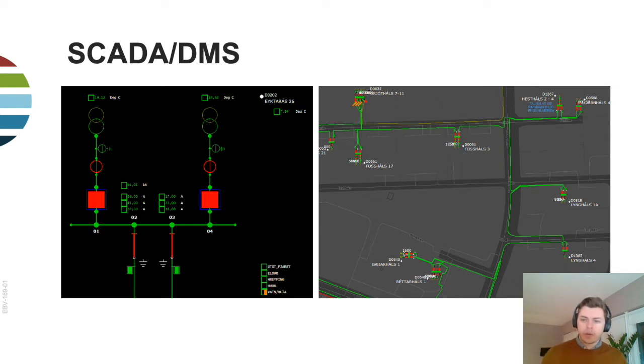For those unfamiliar with what an ADMS looks like, it essentially has a geographic view of all the secondary substations on the 11 kV network, which is our medium voltage. You also have a schematic view of that same equipment, where we connect the SCADA points, if there are any, in the secondary substations, giving real-time values from the equipment and their positioning. One of the core functions of the ADMS is to manage the positioning of all switches and breakers in the network.